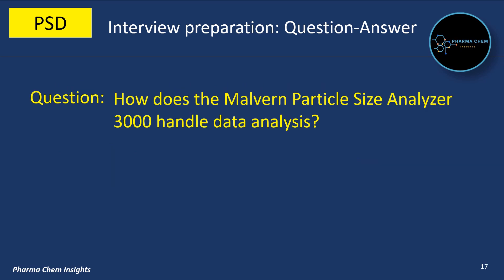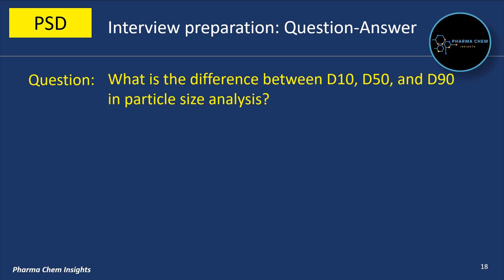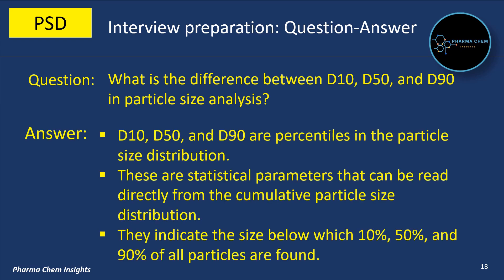How does the Malvern Particle Size Analyzer 3000 handle data analysis? The software provides detailed data analysis including statistical representation, distribution graphs, and trend analysis. What is the difference between D10, D50, and D90 in particle size analysis? D10, D50, and D90 are percentiles in the particle size distribution — statistical parameters read directly from the cumulative distribution, indicating the size below which 10%, 50%, and 90% of all particles are found.